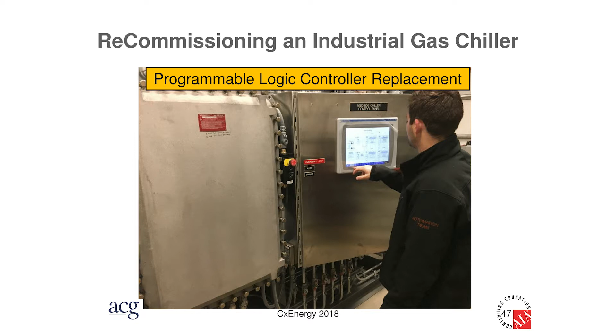Then, if you can read the fine print, I don't know if you can, it starts here. It says, raise the entering gas temperature by 10 degrees, state the conditions, and then we recorded all the conditions right here, and then run for 30 minutes, and then raise the temperature another 10 degrees, and do it all over again. We did that in 10-degree steps.